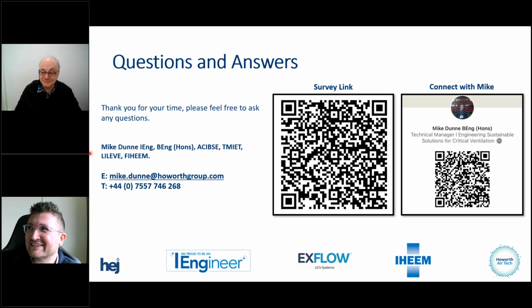Yeah, there's a lot in there. Basically what we do at validation, the first thing we do is be involved from the start if we can, so we'll go through and make sure everybody's familiar with the scope of works and what's required of that system. The second thing when we get to site is we'll run an Appendix 1 and 2 check, the fabric and standard check that would be carried out at the annual verification of the system, which is a requirement in HTM03 Part B. You go to the back of that document, there's appendices in there, and look through them.